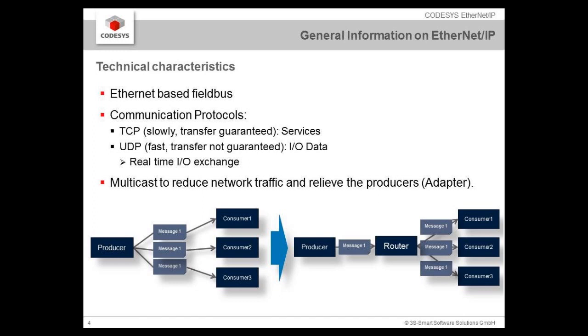Some technical characteristics on EtherNet/IP: it is an Ethernet-based fieldbus using the transport protocols TCP and UDP, whereas TCP is used for services and UDP is the faster protocol for I/O data that we will be using for the real-time I/O exchange.